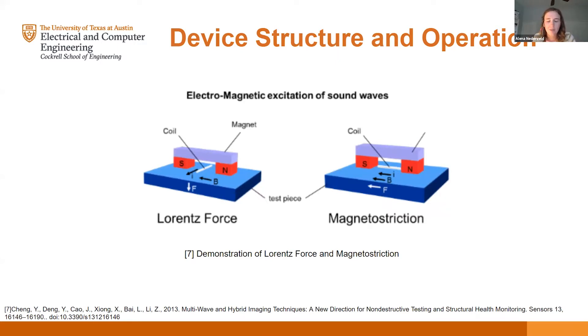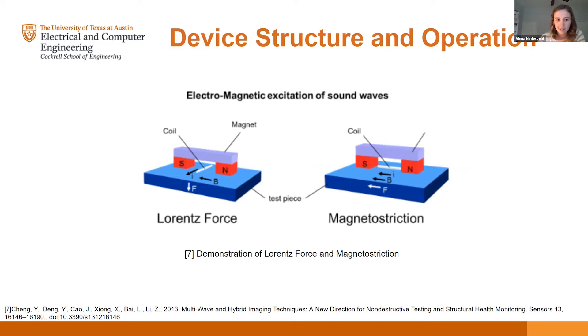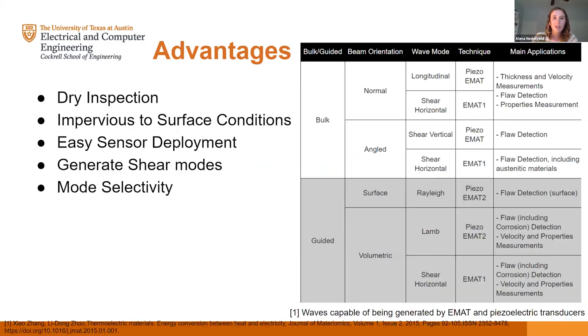Another feature of EMATs is that with ferromagnetic conductors, you get an effect called magnetostriction — the property of ferromagnets to expand or contract in response to a magnetic field. This produces additional stresses that enhance the signal to much higher levels than could be obtained by the Lorentz force alone. The catch is that you have to be working on something ferromagnetic for this effect to aid the EMAT.